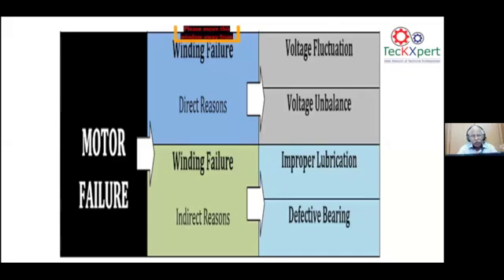Though the EB gives an excellent voltage supply at the input, why the unbalance is coming, we'll see in the next slide. But on the indirect reasons, many of the motors fail due to improper lubrication, which we come across now. And it's a defective bearing, where the lubrication and the bearing are not rightly matched to the existing motor condition. This also matters more. In some places, we have even started changing some of the ball bearings to roller type bearings so that the area of contact is increased and the heat is dissipated more on a roller bearing compared to a deep groove ball bearing.